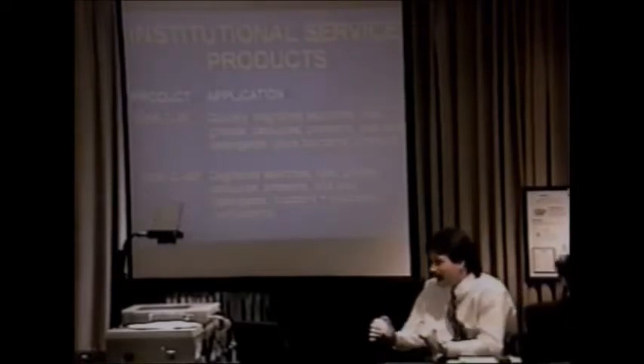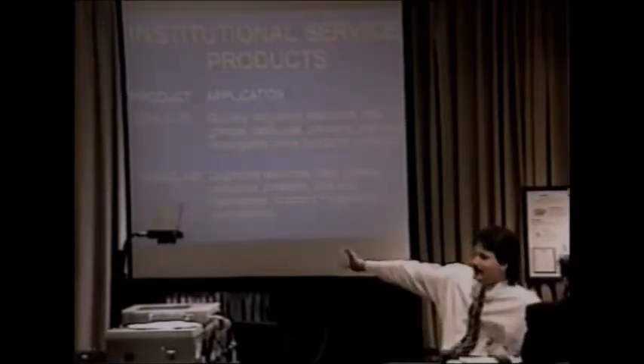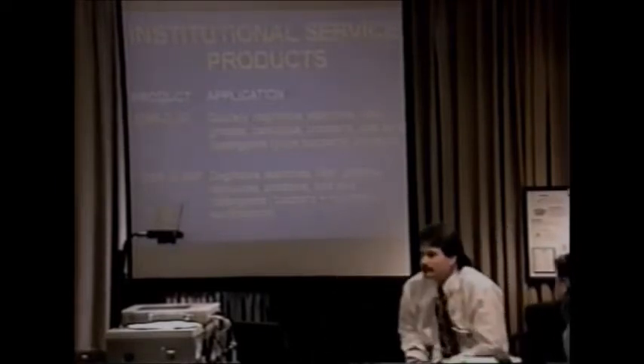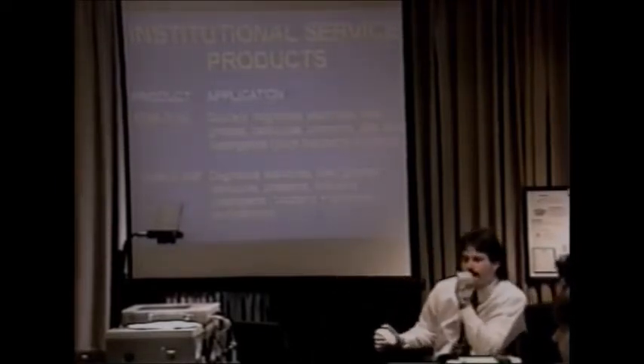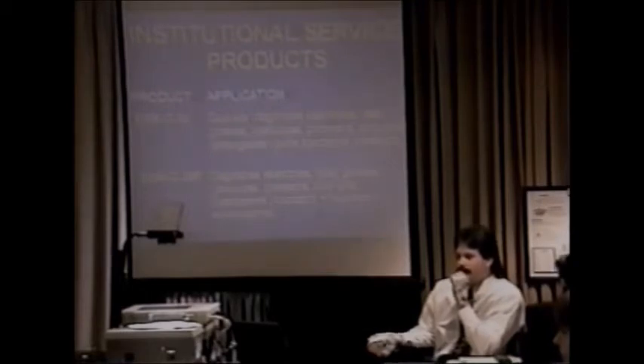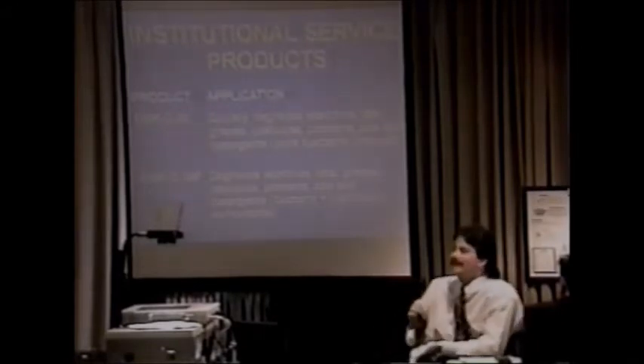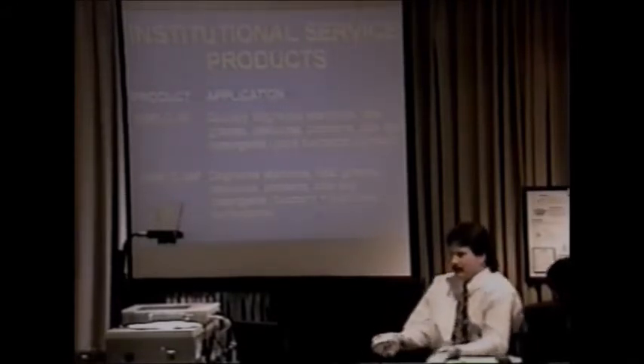Eliminate it out of the grease trap, but not eliminate it down the line to the POTW, or the ditch or wherever it goes. And the one thing that's nice is when they do get a clog up, the only way to clear it is chemically first, and then they've got to restart. This is not an opener. Bacteria are not an opener. They are a maintenance, a preventive maintenance.